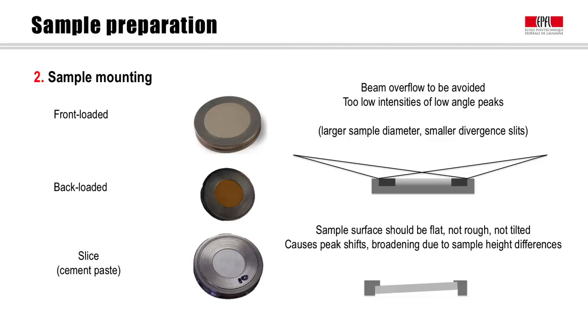In mounting the obtained powders and slices onto the sample holders for quantitative XRD, the following aspects should be considered. In flat plate reflection geometry, care should be taken that the sample surface area and thickness are large enough to avoid any beam overflow at low angles. Too small surface areas will lead to an underestimation of peak intensities at low angles and may also cause increased background from the sample holder. In case smaller sample holders are used, one can change the diffractometer optics by choosing smaller divergent slits.